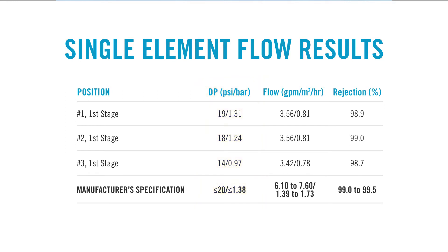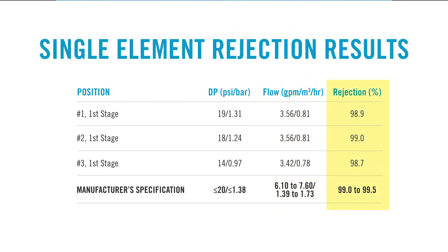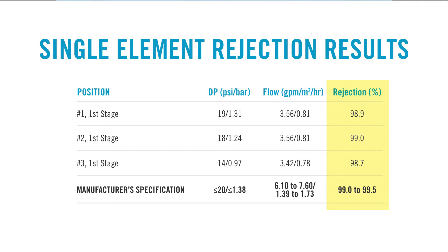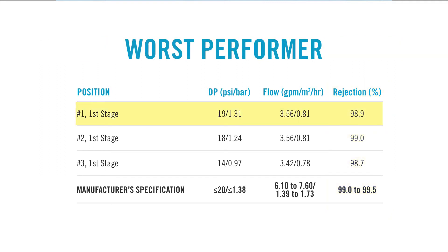We'll also take a look at their flow. The flows were fairly consistent for the first three elements in their system, with about half of their original performance. Another thing we'll look at is the rejection. We'll note that the rejections are similar, but slightly below normal. So let's take a look at the first element from the first stage. We see the delta pressure is 19, the flow is 3.56 GPM, and the rejection is 98.9%. We selected this element because it's the worst performer. So if we can find a solution for this element, we can find a solution for the whole system.